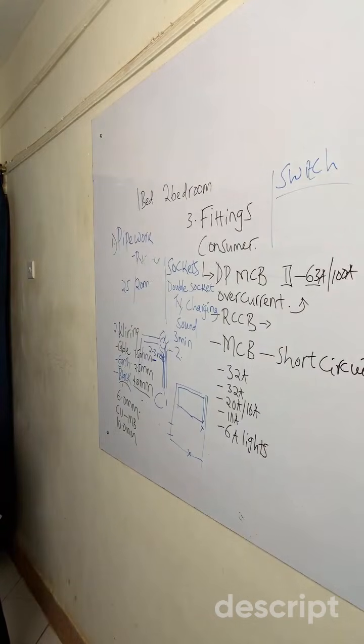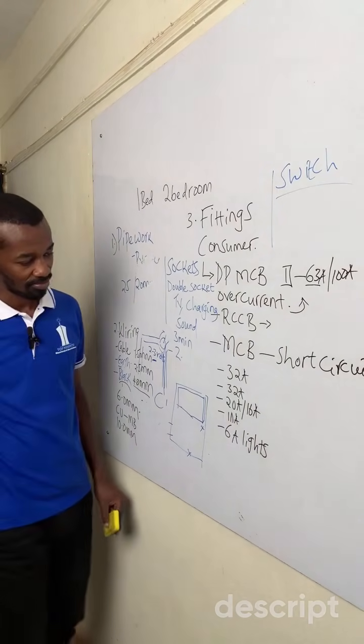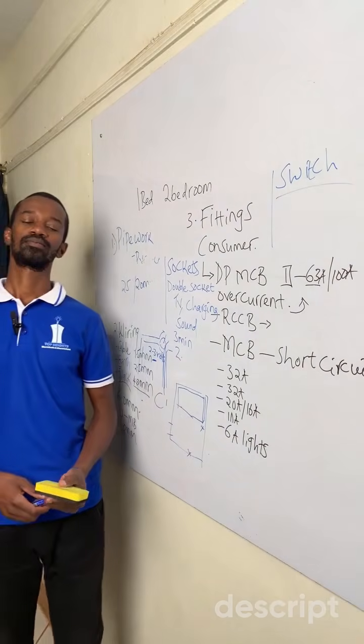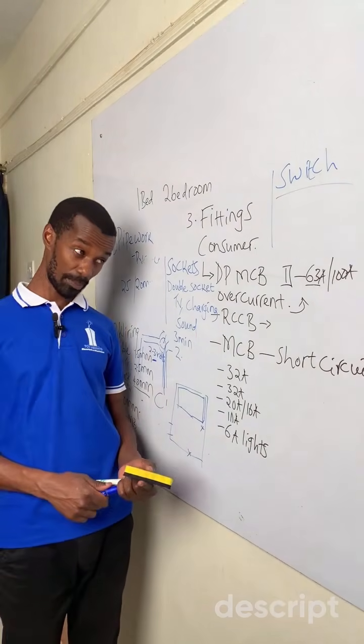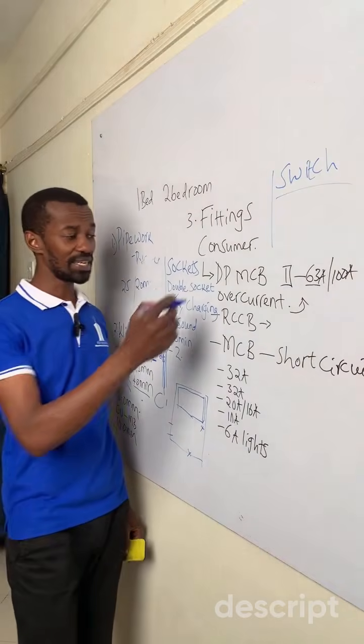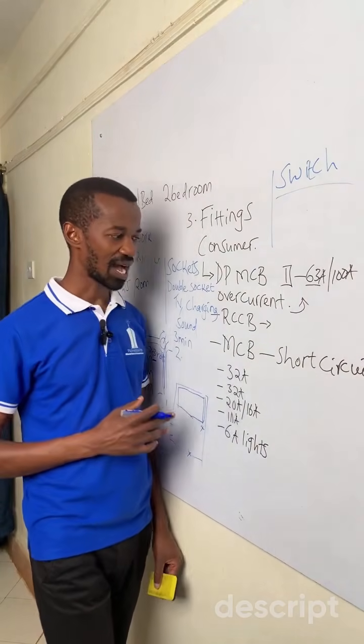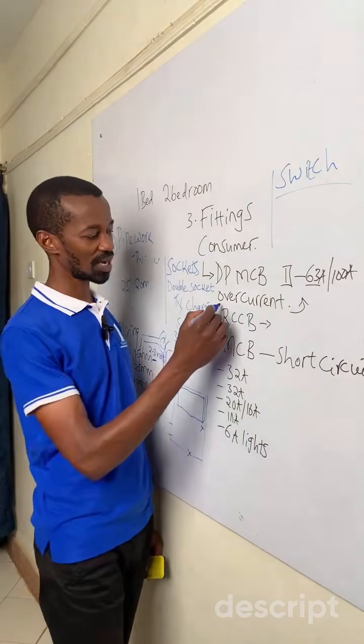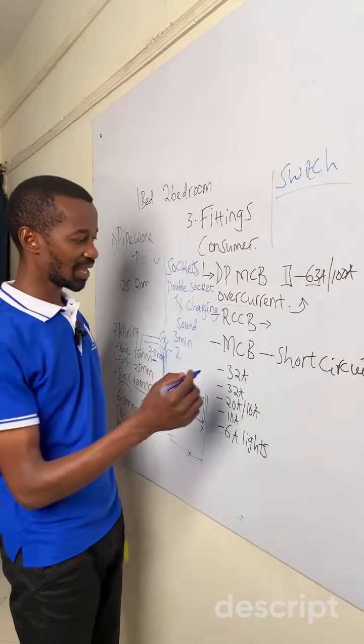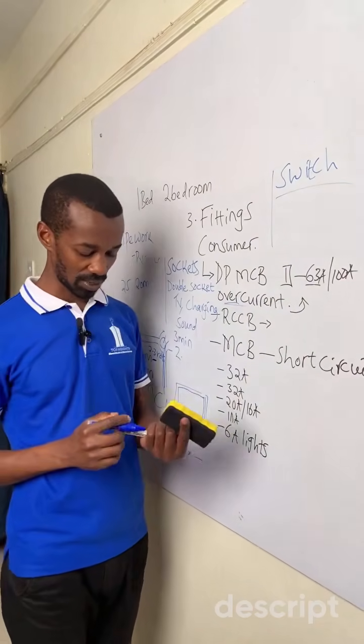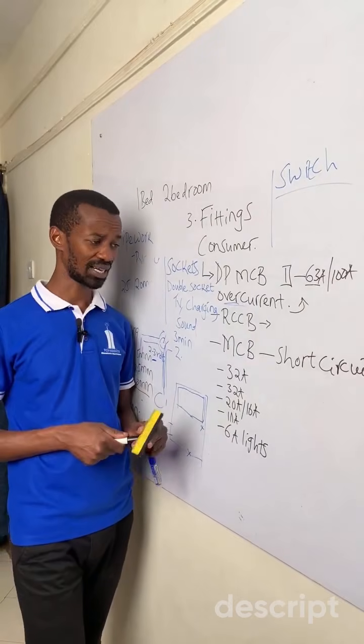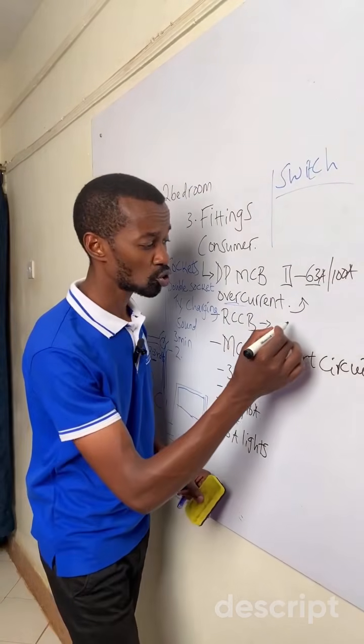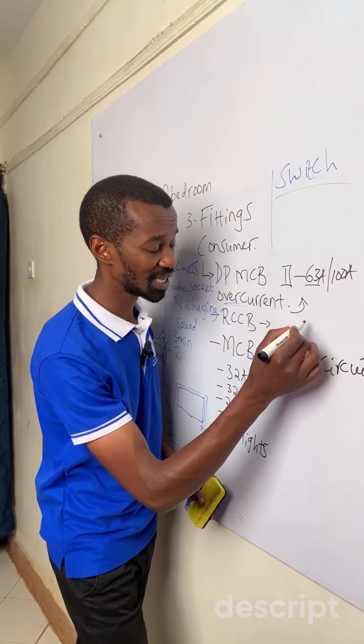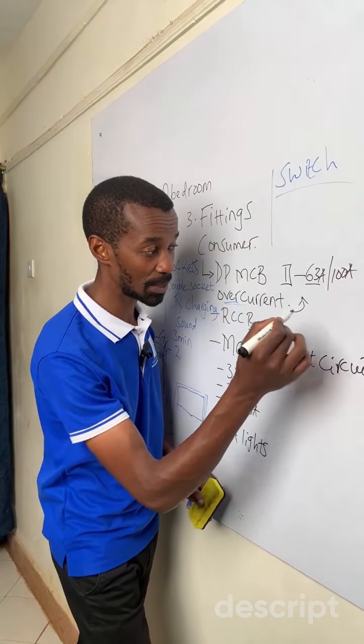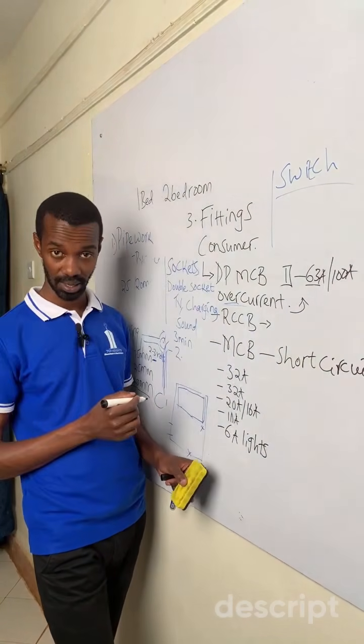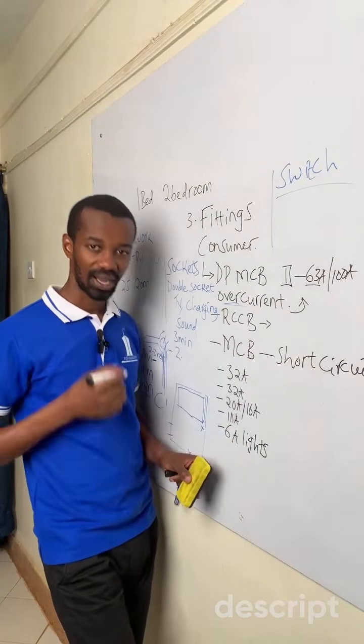Please, can you re-explain the DP MCB? The DP MCB first has to protect against what we refer to as an overcurrent. When it comes to overcurrent, we want to know what that is. First, if the total load connected at a given time exceeds the rating of the DP MCB, it means it will trip, protecting against that overcurrent.